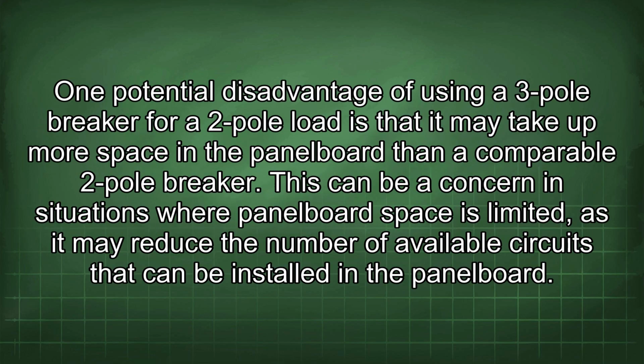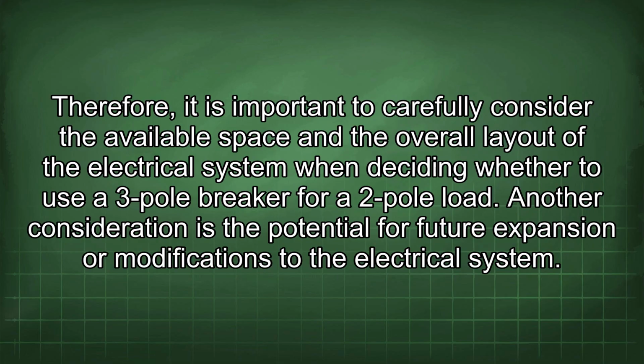One potential disadvantage of using a 3-pole breaker for a 2-pole load is that it may take up more space in the panel board than a comparable 2-pole breaker. This can be a concern in situations where panel board space is limited, as it may reduce the number of available circuits that can be installed in the panel board. Therefore, it is important to carefully consider the available space and the overall layout of the electrical system when deciding whether to use a 3-pole breaker for a 2-pole load.